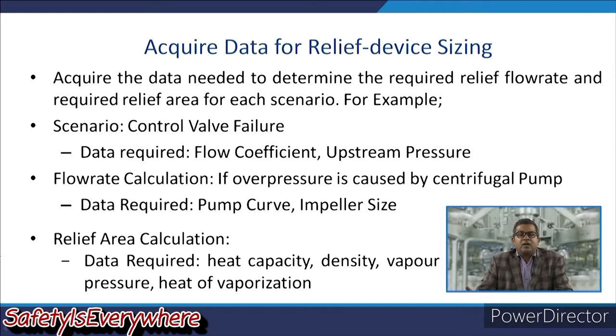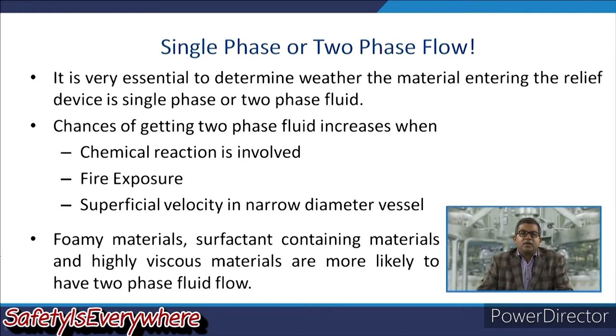Now it is very essential to determine whether the material entering the relief device is under single phase or two phase operation. The chances of getting two phase fluid increase when there is a chemical reaction involved or something going on in the intermediate phase. There may be chances of fire exposure, superficial velocity in a narrow diameter vessel, or phase transformation. Foamy materials, surfactant containing materials and highly viscous materials are more likely to have two phase flow.